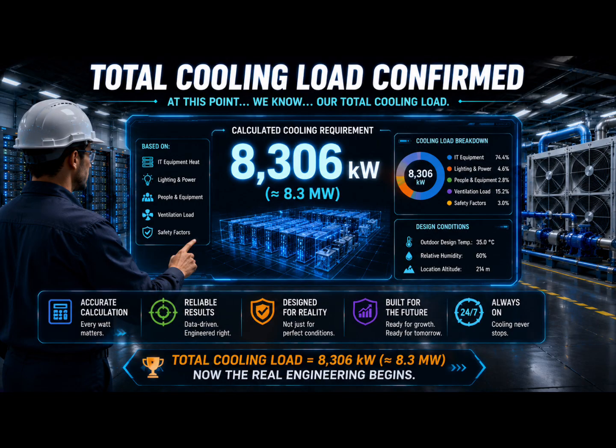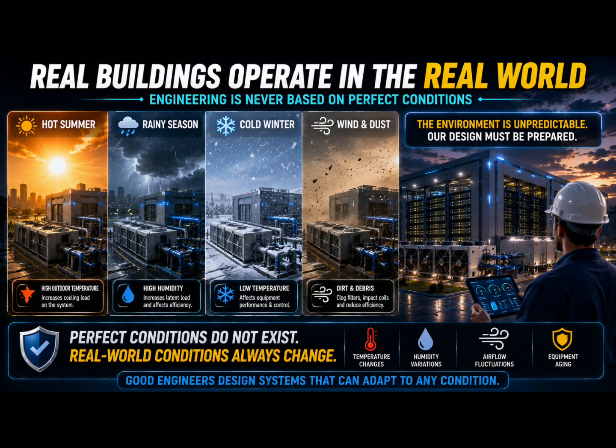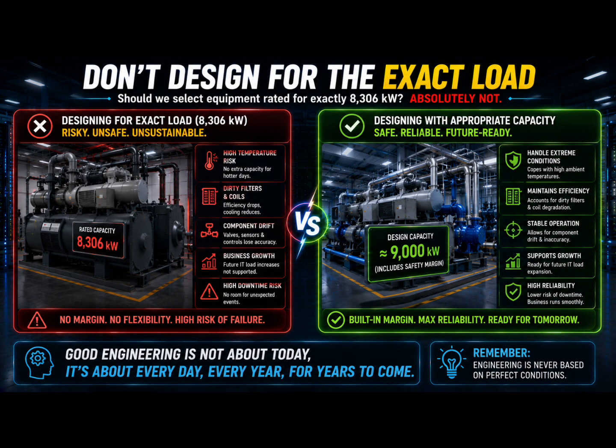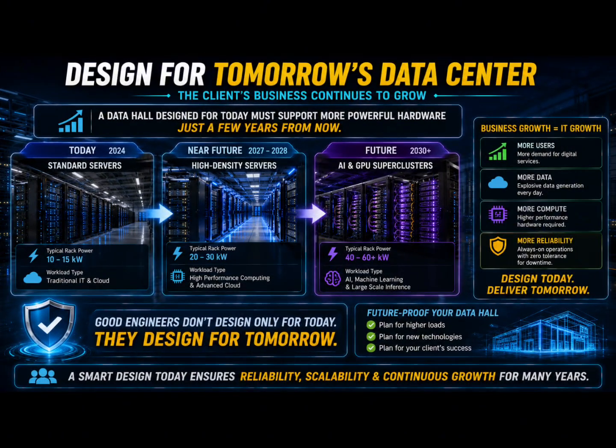At this point, we know our total cooling load, 8,306 kilowatts. So, should we simply select cooling equipment rated for exactly 8,306 kilowatts? Absolutely not, because engineering is never based on perfect conditions. Real buildings don't operate inside a laboratory. Outdoor temperatures change, humidity changes, air filters become dirty, heat exchangers slowly lose efficiency, control valves drift, sensors become less accurate, and perhaps most importantly, the client's business continues to grow. A data hall that is designed for today's servers may need to support more powerful hardware just a few years from now. Good engineers don't design only for today.